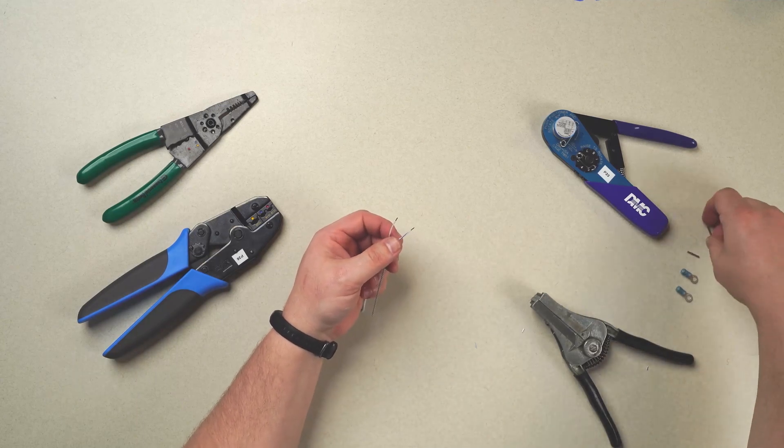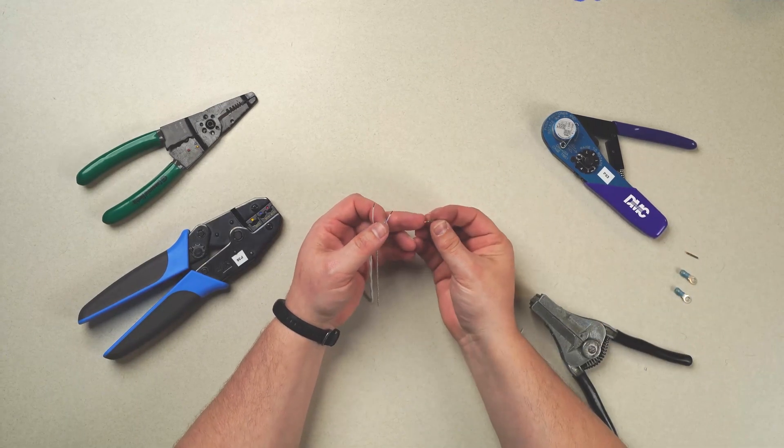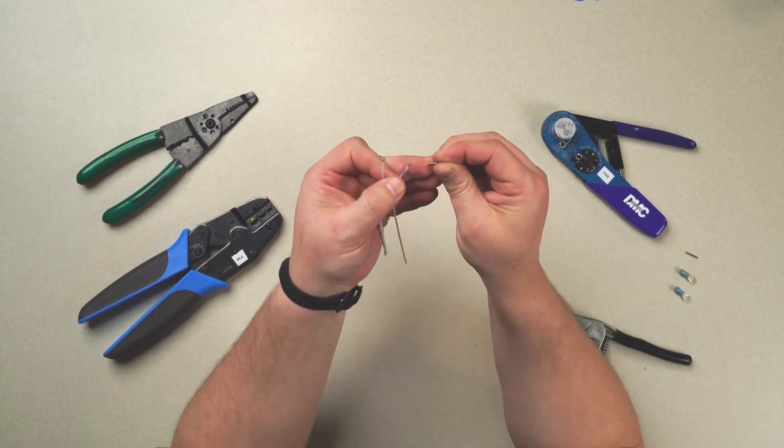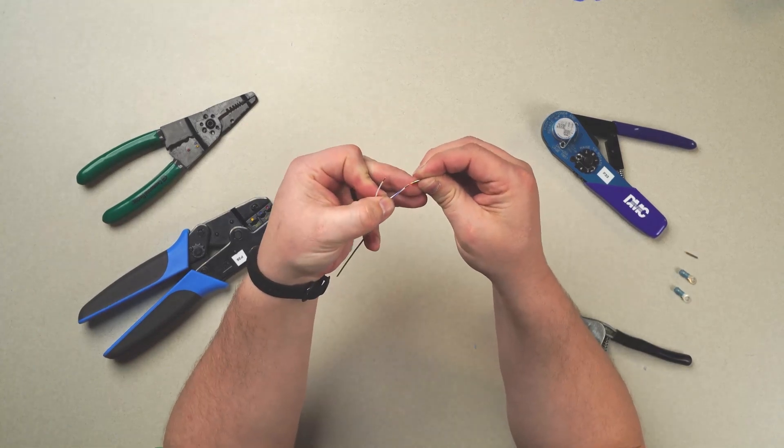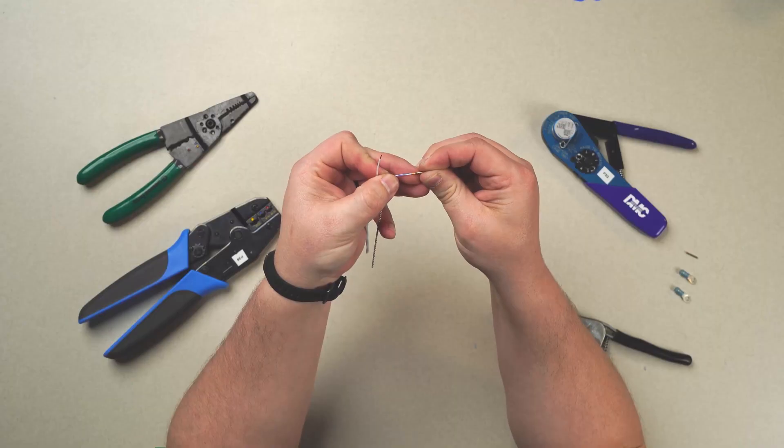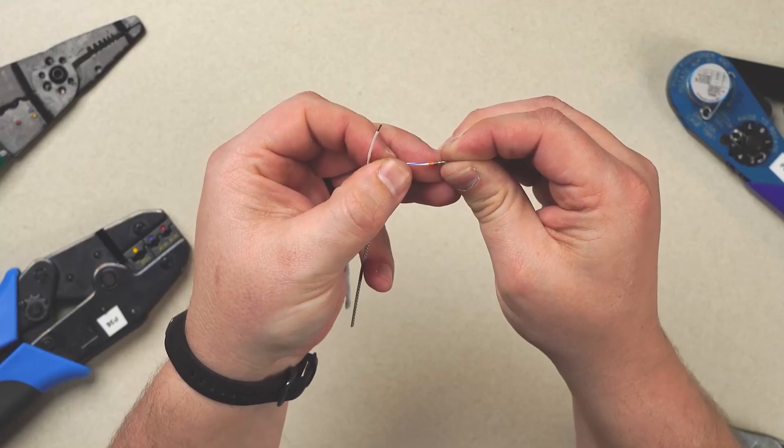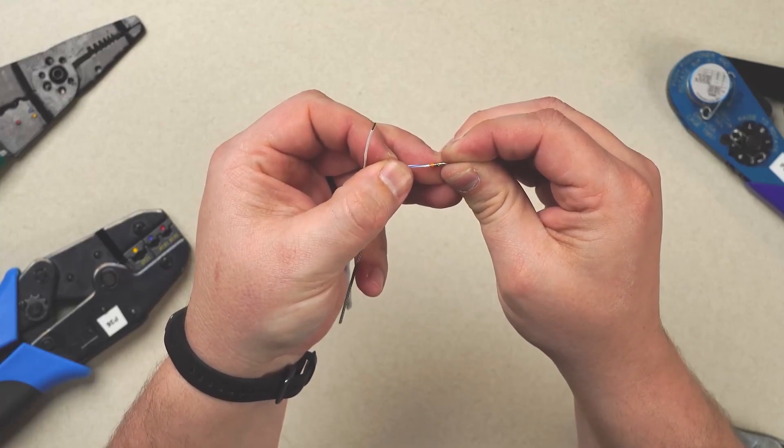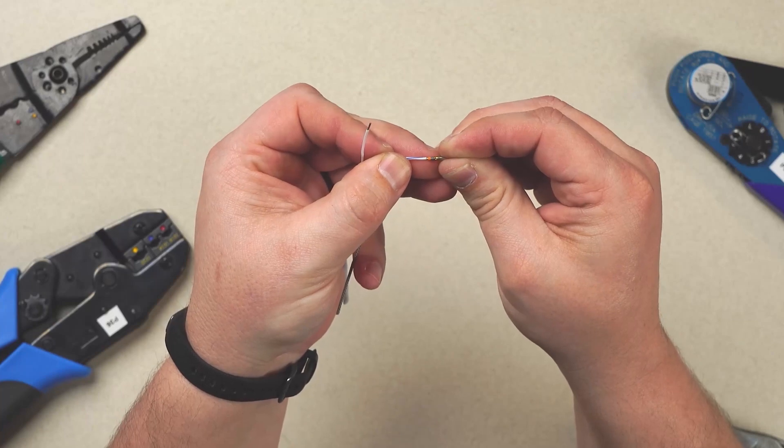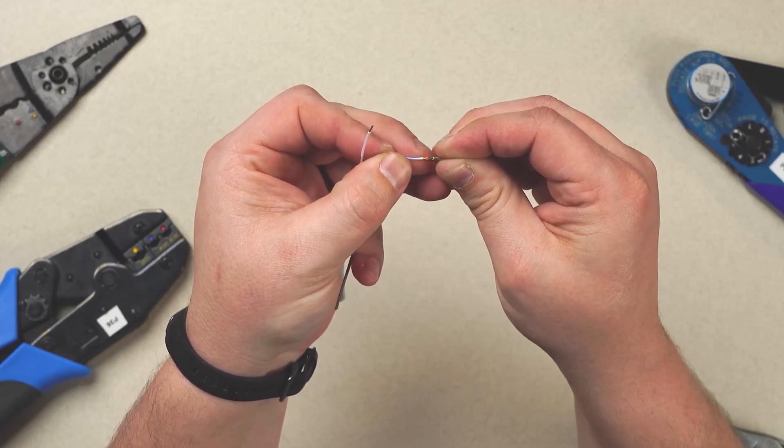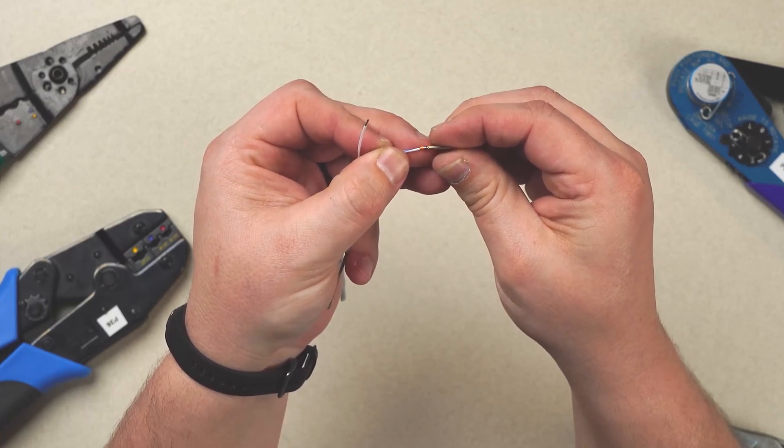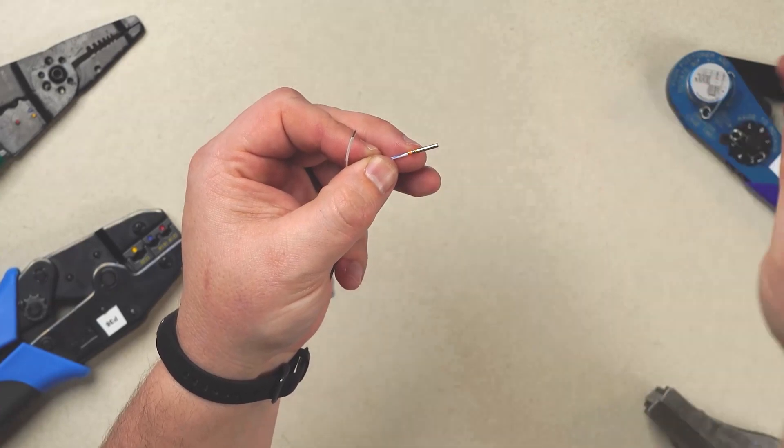Establishing the proper length of the strip, you can actually tell by utilizing the window here on your pin. And you'll see that the wire actually slides in and stops. And there's still just a squish of exposed wire before you see the insulation. So we know we're bottoming out in the pin or socket correctly.